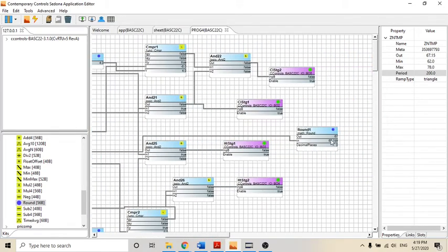So here we are at 67 degrees. Right now we are at set point, so our differential says we need to get to at least 1 degree below that. As we approach that, we'll see it go on. There we go. We get to 65 degrees and we have our heating stage 1 go on. And then as it cools off, we will see the heating stage 2, here it is, go on. Now our temperature reaches the lowest point and it starts going up, and the cycle goes on and on.